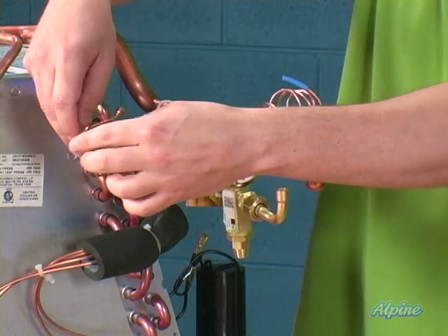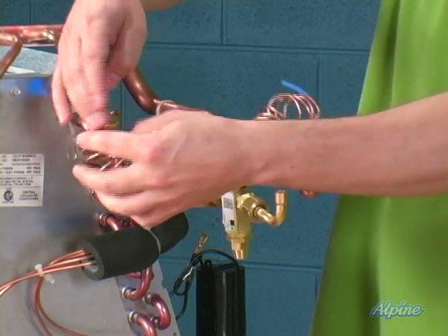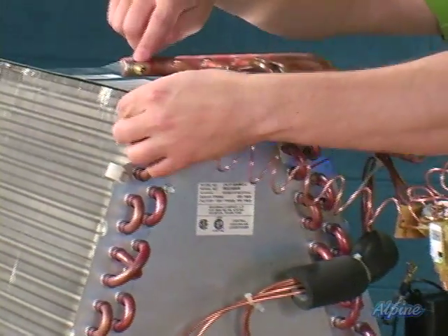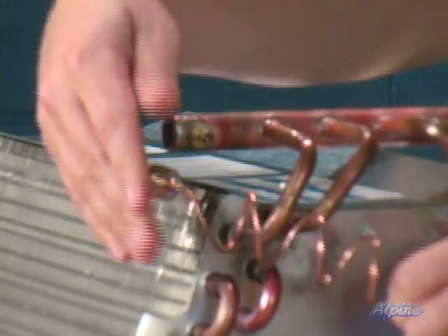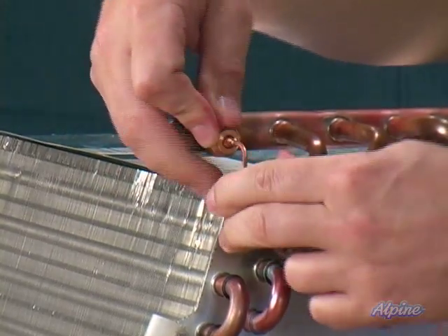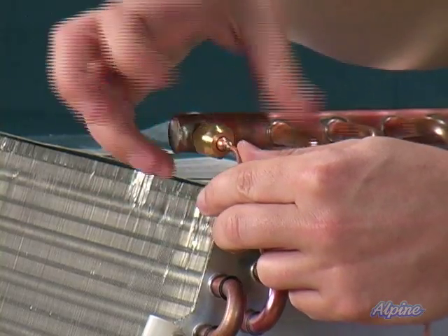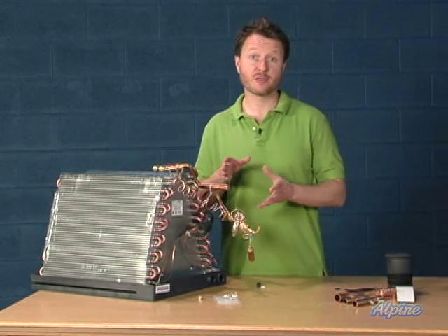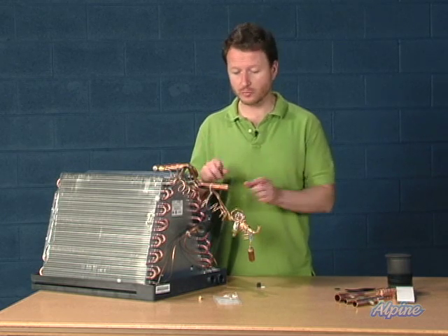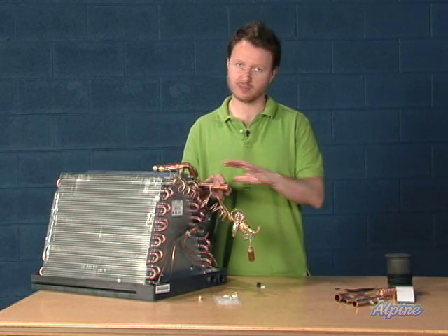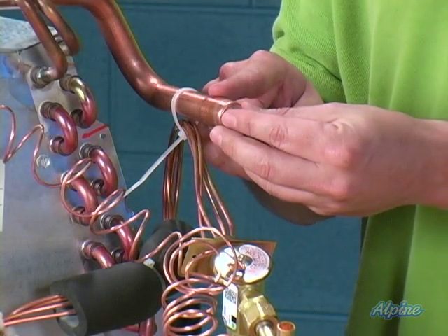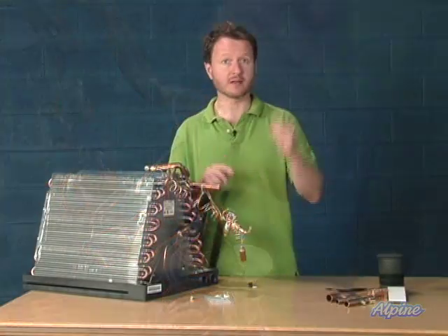Then I've got this tiny little piece over here, and it has a flare fitting that screws right onto this part of the coil. Now, most new coils will have a little spot to screw that on simply, like so. Of course, these will be snugged up with wrenches as needed. Once we've got that thermostatic expansion valve installed, as usual, this pipe still needs to be hooked up as it normally does in any installation, which would be to cut off the end here and solder in the suction line.